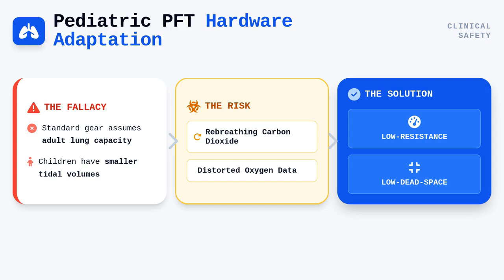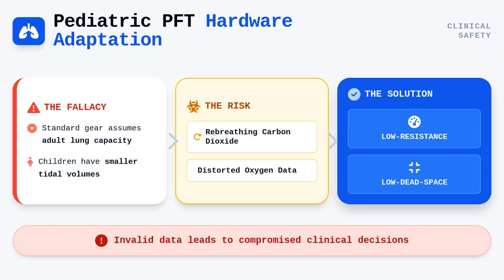We combat this by implementing low-resistance, low dead space breathing valves, which are critical to preventing the patient from inhaling their own exhaled carbon dioxide. This rebreathing artifact can falsely lower the measured oxygen partial pressure and distort the measured ventilation, leading to invalid diagnostic data that could compromise clinical decisions.